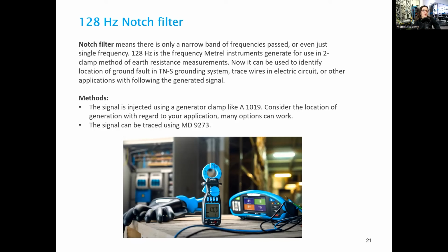So the main application deals with locating an installation failure. The signal is injected into the main grounding wire, and if there are no problems, it just flows into the ground. However, if there is an installation failure, the signal will be pulled into the local protective earth connection and returned by one of the other lines. So it is possible to track where this circuit is connected so that the signal can return. The application works much better in a TN-S grounding system, where the impedance of the grounding system is very low, which leads us to very low noise and a high generated signal.